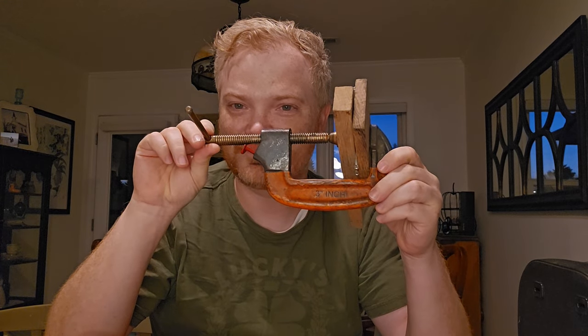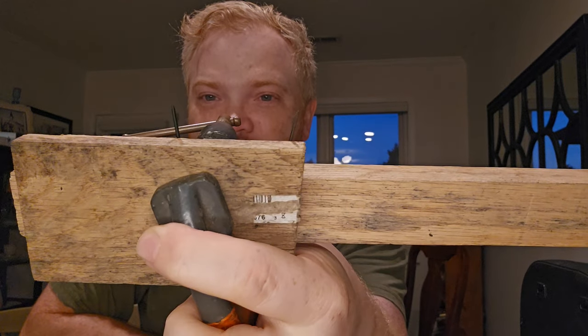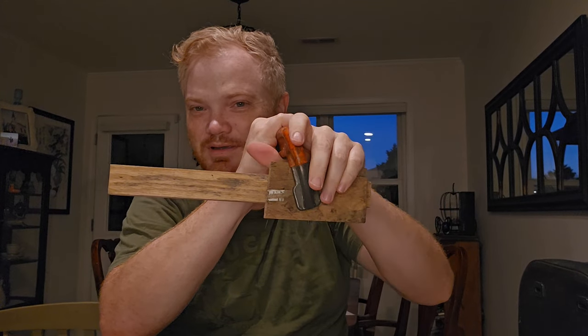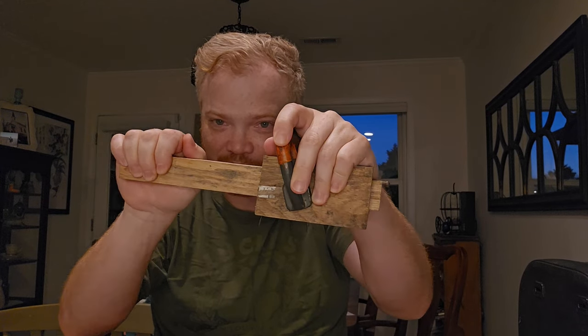What I have done is I went and got a C-clamp, some wood, and some very small screwdrivers, and I made a tool that I can then go in and brace into the mechanism here and tweak it ever so slightly. No banging, no forcing anything. It's not the Zeiss tool, which would probably cost thousands of dollars, but it does exactly the same thing as the Zeiss tool for free.